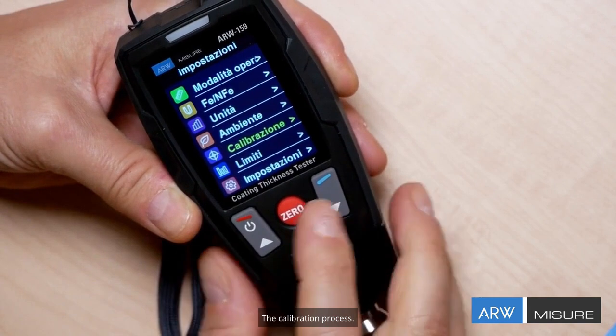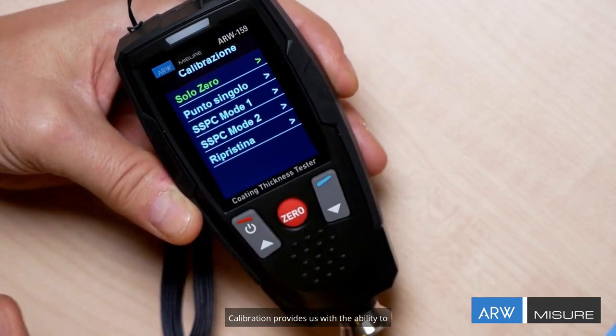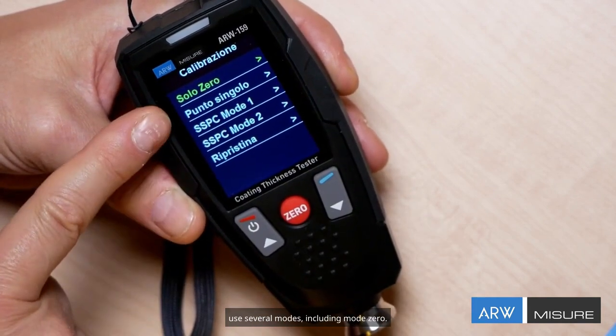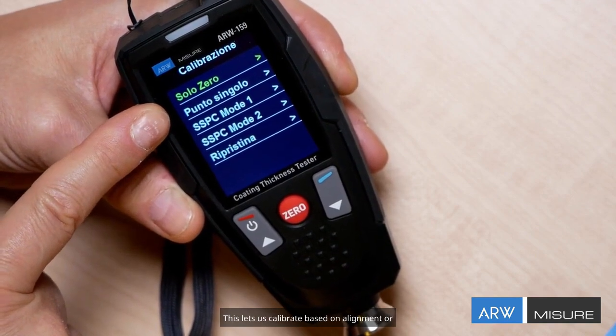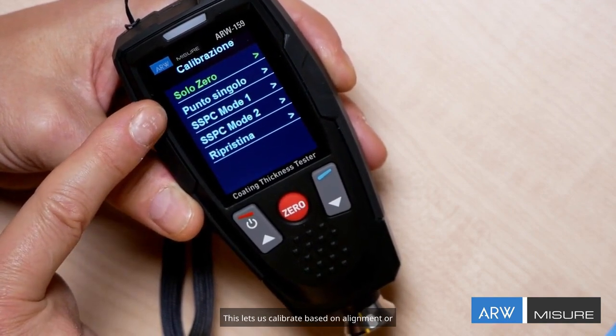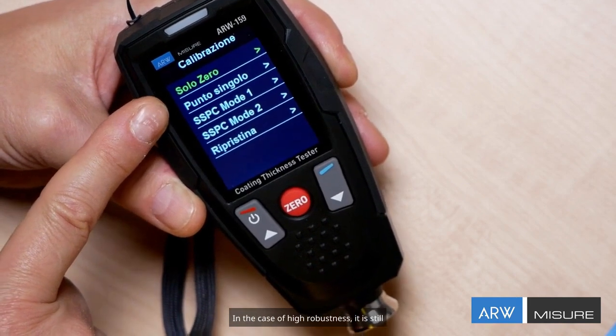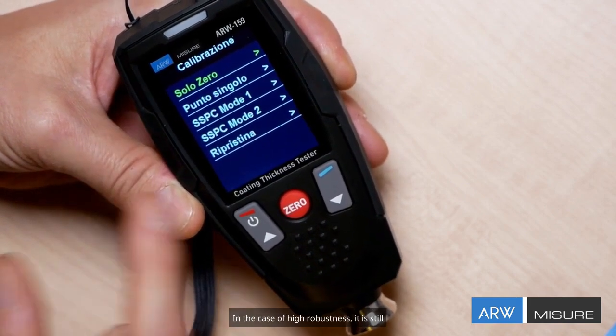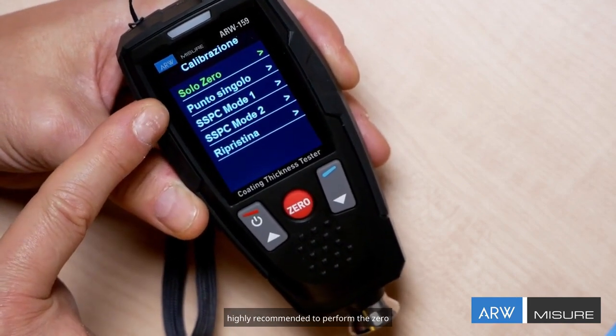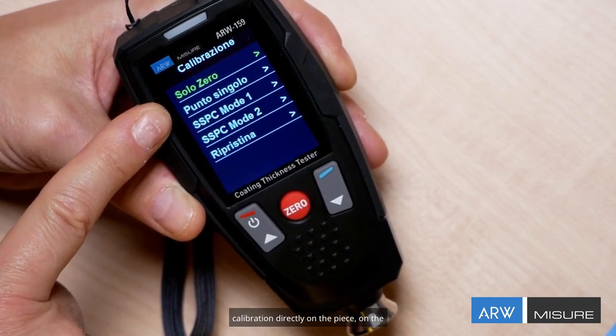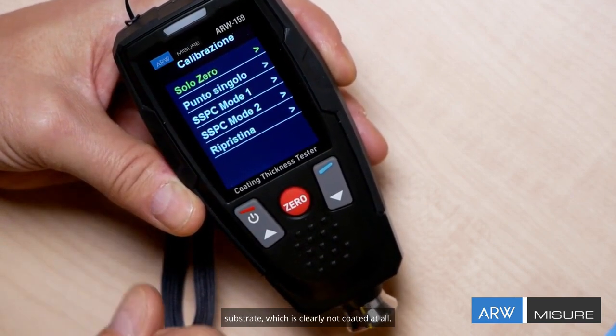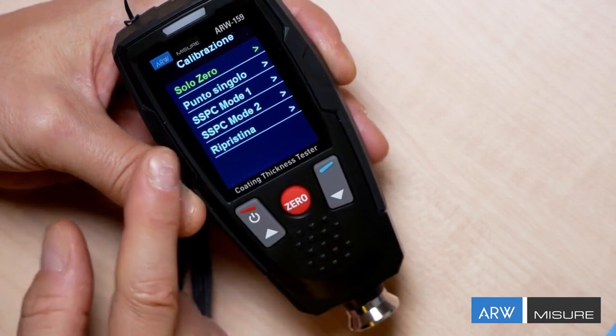The calibration process. Calibration provides us with the ability to use several modes, including mode 0. This lets us calibrate based on alignment or on a specific sample piece. In the case of high robustness, it is still highly recommended to perform the 0 calibration directly on the piece on the substrate, which is clearly not coated at all.